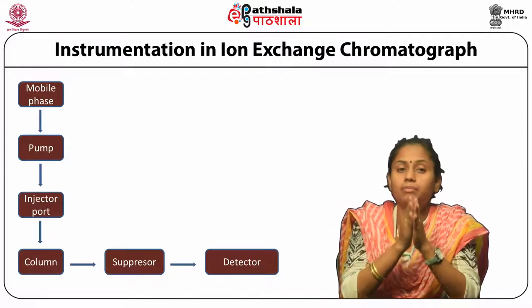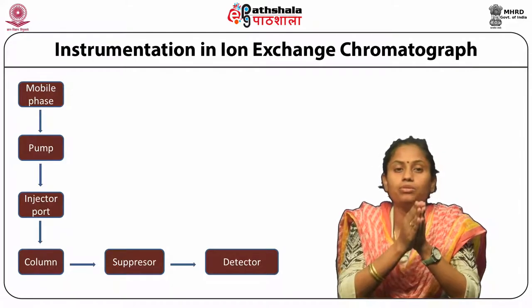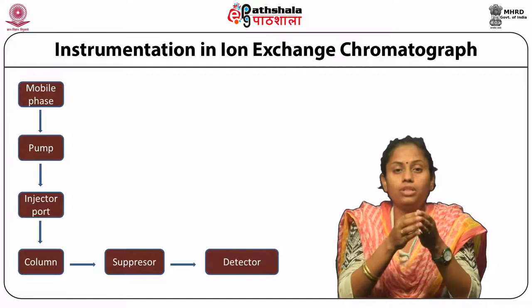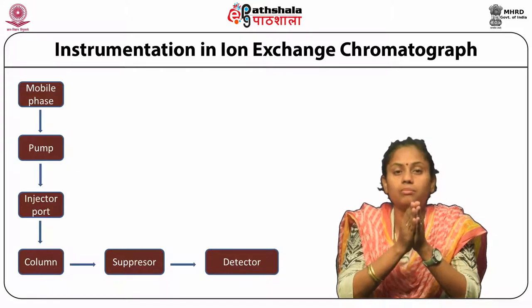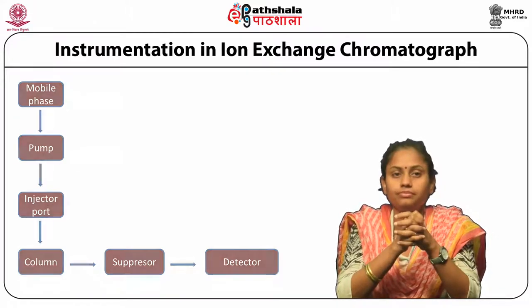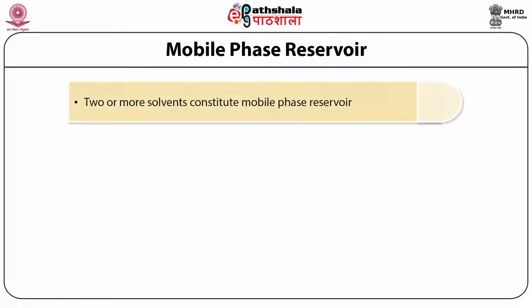The complete setup of Ion Exchange Chromatograph is managed by a computer-aided software which acquires and processes the data obtained during the complete chromatographic procedure. Now, let us talk about the different components used in Ion Exchange Chromatography. To begin with, the very first step is the selection of a mobile phase. In Ion Exchange Chromatography, there can be two solvents or more which are blended according to need to form the mobile phase reservoirs.